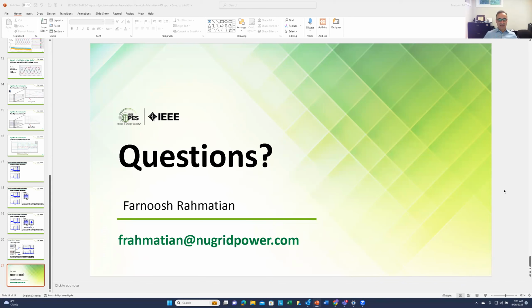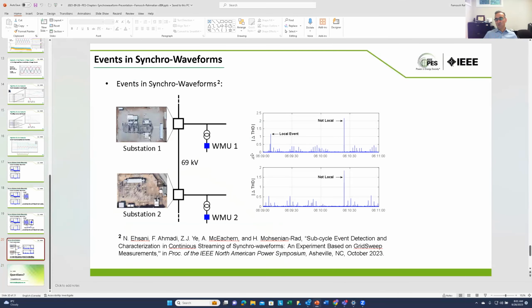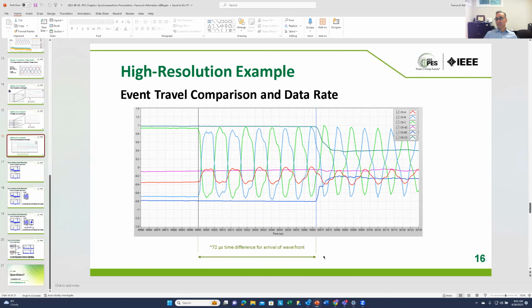You're right. The example you saw here is from standard power quality meters, which also have waveform, so they only look at those. But if you use a device like this, that has megahertz capability, and look at true THD, true to its bandwidth, then that's different. You're exactly right. If you use THD, you're limited by the definition of that particular THD, that particular device. Most relays, most devices are designed with anti-alias filtering for good reason, to filter out anything really high frequency and only look at the few harmonics that the standard asks them to look at.